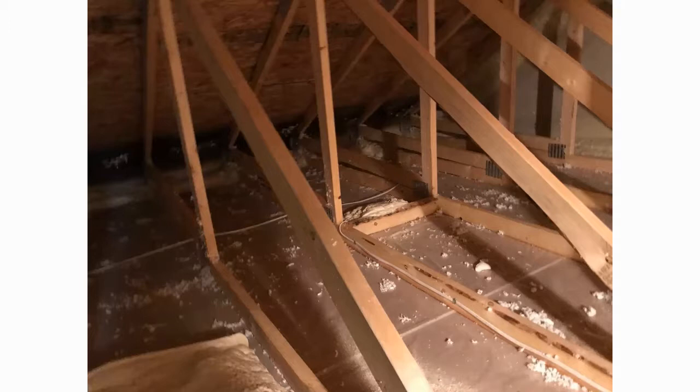But on the old homes, we have to do what we can to stop the water from coming into people's bathrooms. So we have a short collection route, or a loop, I guess, that will hold that condensation. If we make that loop too tight, imagine a P-trap under a sink, it will actually act like a P-trap and stop the flow of air, and that's not good.